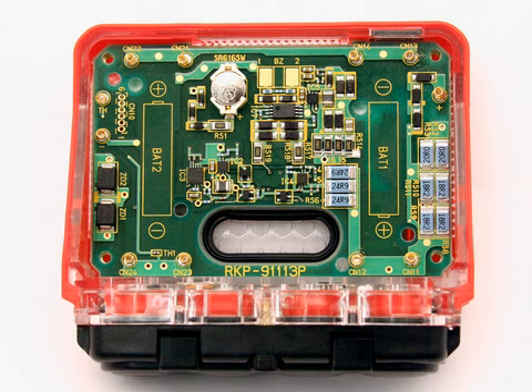The primary function of the GX-2009's printed circuit boards is to amplify the signal sent to them from the four gas sensors, convert the signal to a measurement of gas concentration, display the gas concentration on the LCD, store peak, STEL, and TWA readings, and activate the alarm circuit if an alarm point has been reached. The circuit board also monitors battery level, battery failure, and sensor failure. They also control the GX-2009's time function and various operating modes.